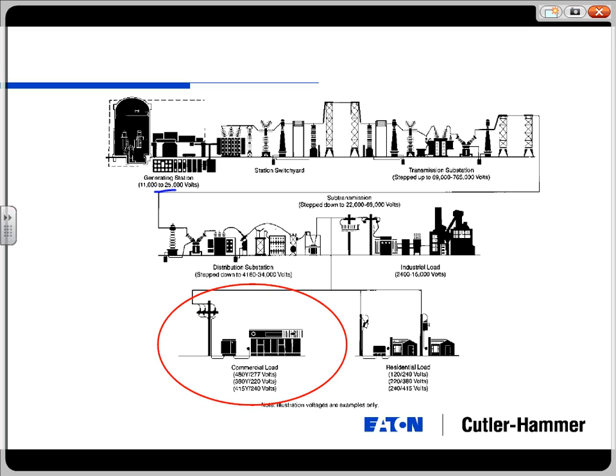And then when they get local, back into a certain area that's going to use the power, you'll step it down into a distribution substation, typically down around 34 kV, maybe as low as 15 kV. And then from there, you start farming into your different loads. So your different loads are an industrial load, a residential load, and what we're going to talk about today with panelboard switchboards is the commercial load. And they all have their own different voltages that they use. And just in this range from I'm making power to I'm using power, you can go through 4 or 5 different voltage levels. Anybody have an idea why we need all these different voltage levels?